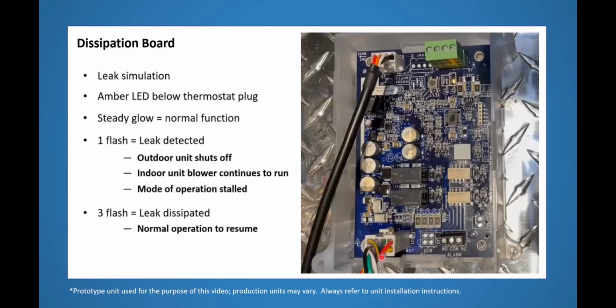Because all this board does is it sits between the thermostat and the equipment. So the thermostat calls for heat on W. Instead of going to the equipment, it goes into this board on W in, and it leaves on W out and goes to the actual equipment. And this board has the ability to blockade the heating and cooling call if needed and force the fan on.